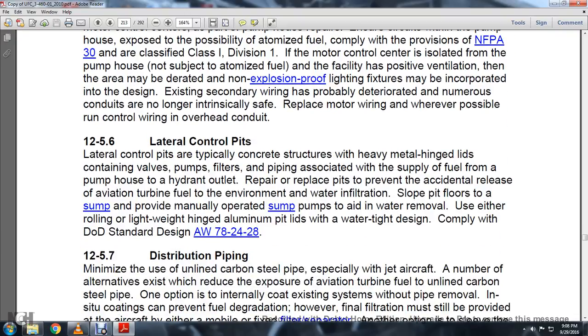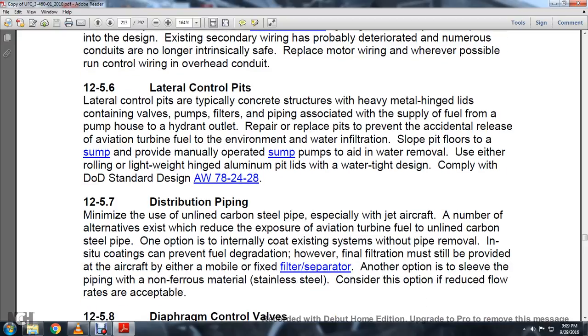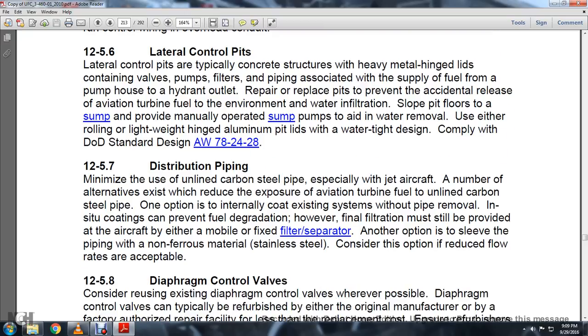Section 12-5-6: Lateral control pits. Lateral control pits are typically concrete structures with metal hinged lids containing valves, pumps, and filters associated with the fuel pump house and hydrant outlet. Repair or replace structures to prevent accidental release of aviation turbine fuel and environmental contamination. Slope pit floors to a sump with manually operated sump pumps to aid in water removal. Replace rolling lightweight hinged aluminum pit lids with a watertight design, per Department of Defense Standard Designs AW 78-24-28.